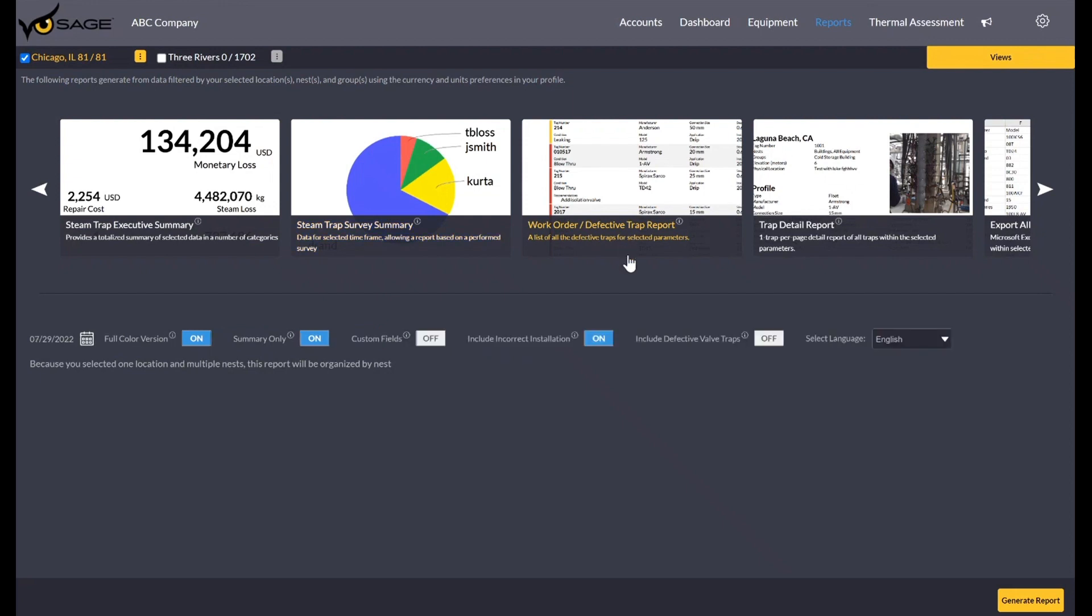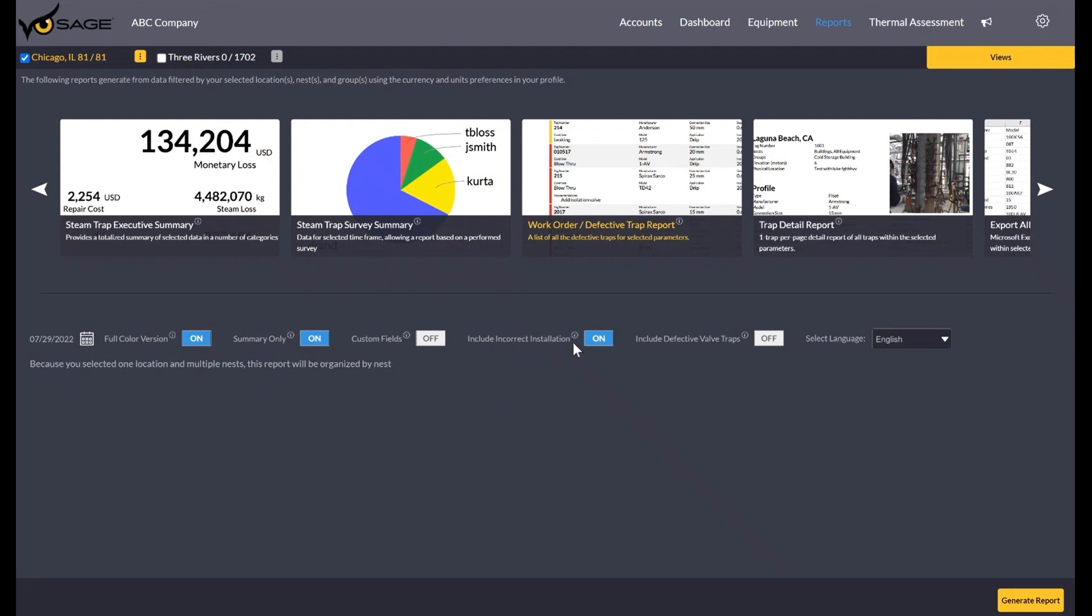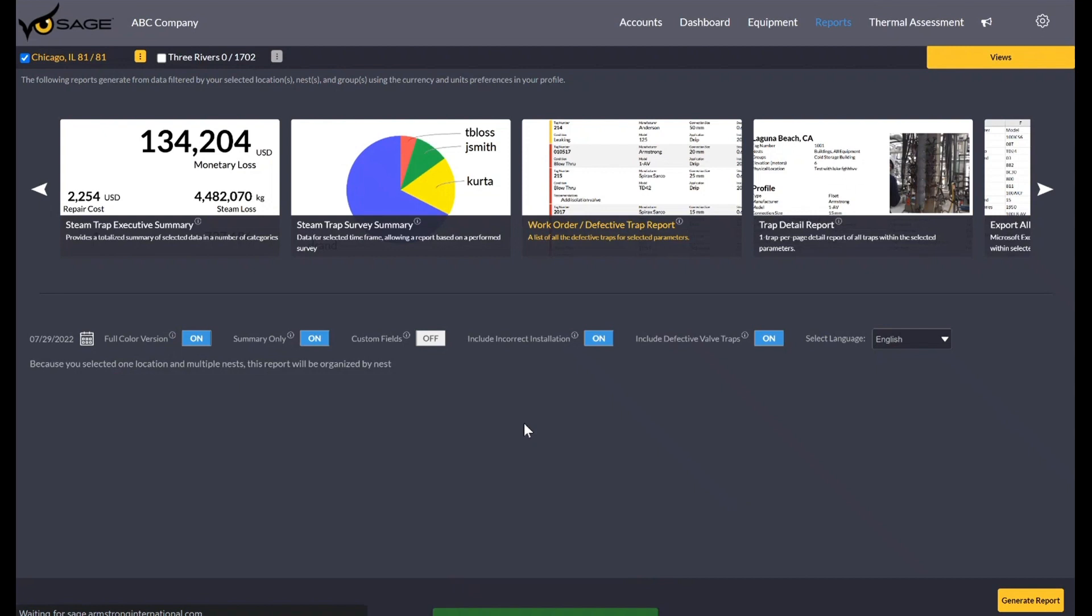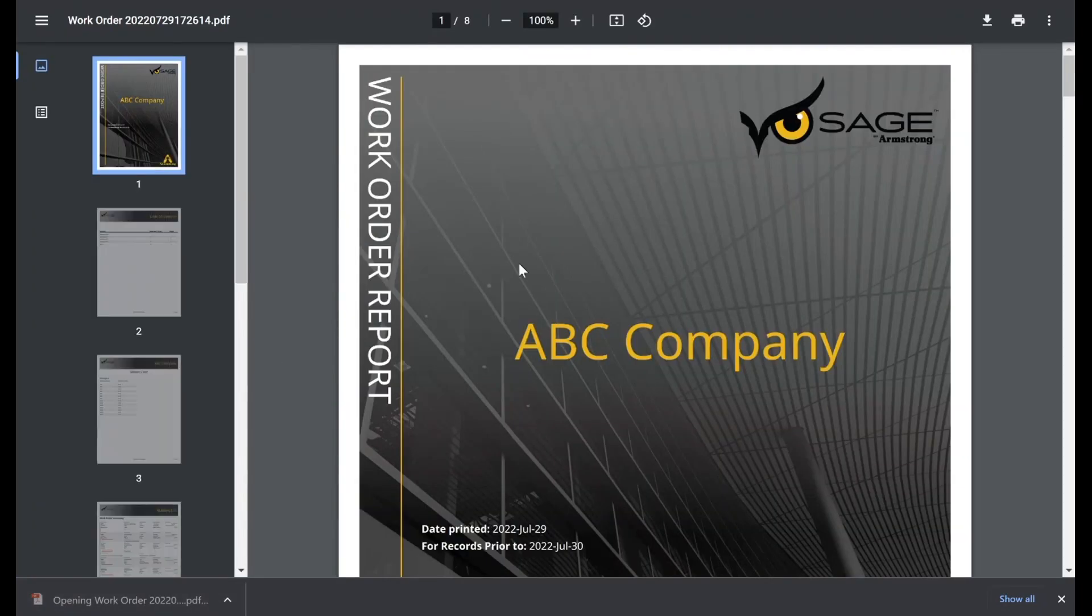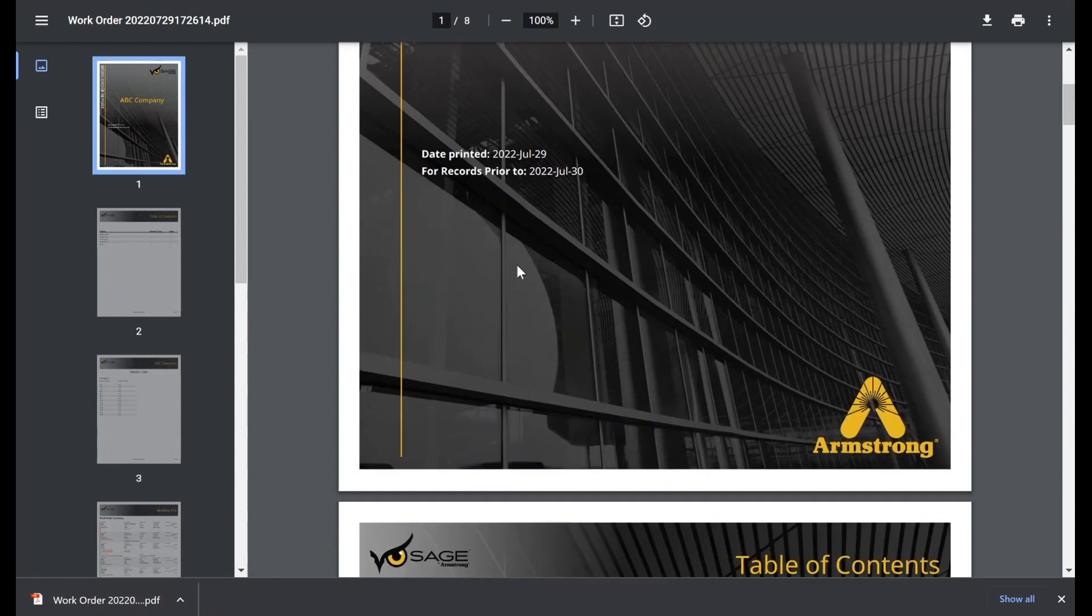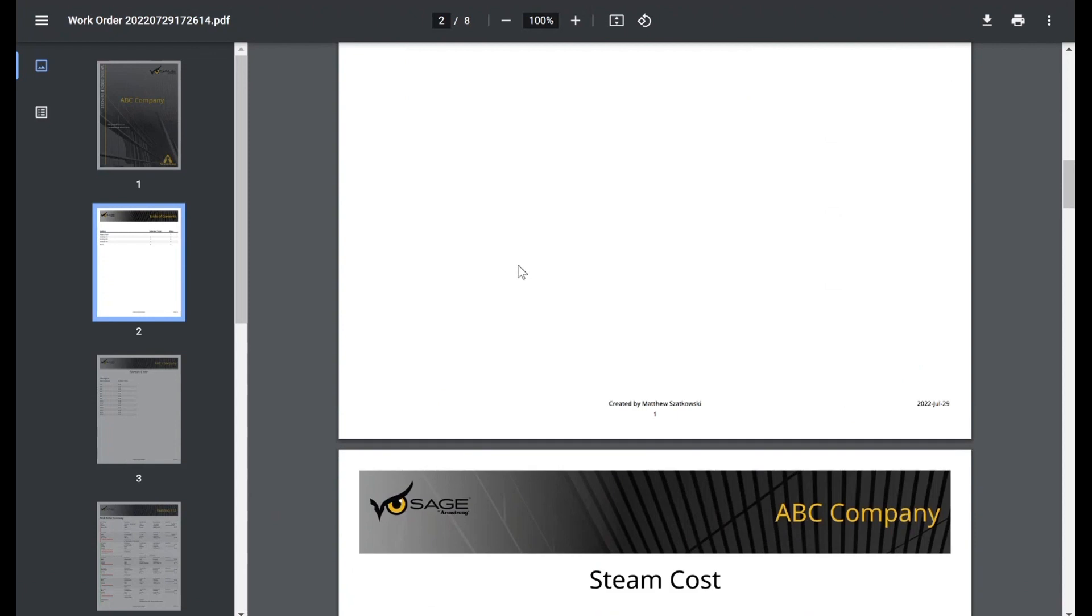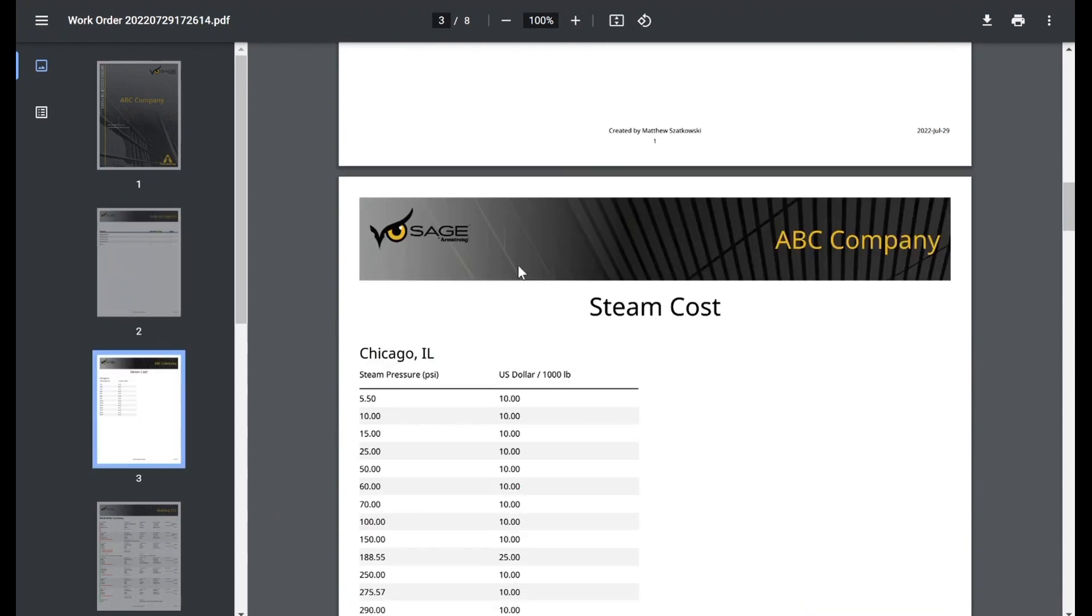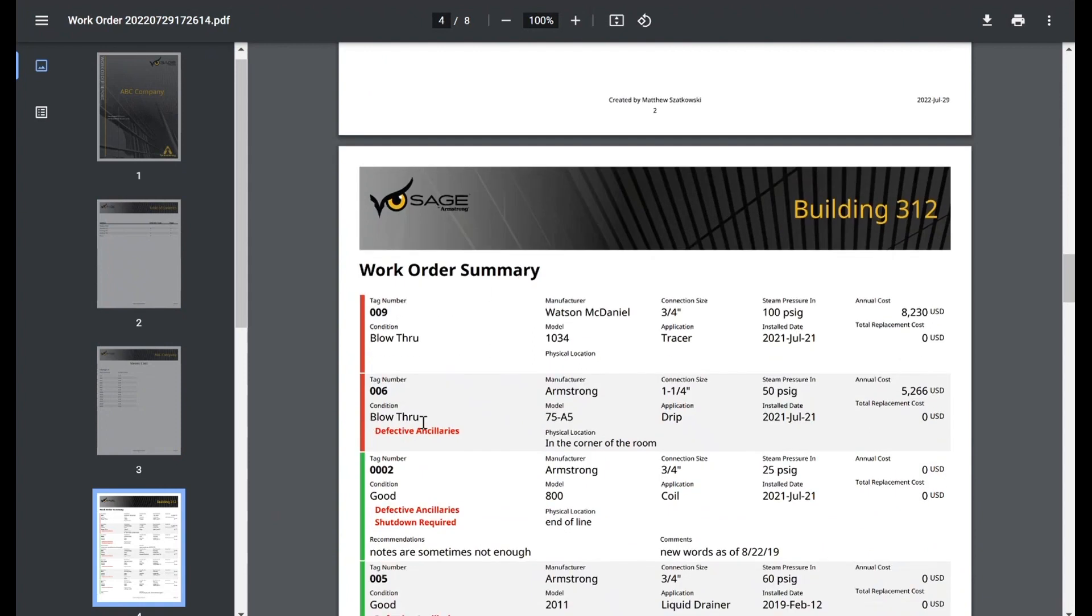The next report here is the work order defective trap report. This is going to report on any failures in our system. Again, the default, like the steam trap executive summary, is today or the day you've entered the system. You can always run a historical version if you'd like to look at historical records. And this one by far has the most customization to the report. As you can see, you have the option to include the incorrect installation toggle and defective valves. So as I went over both of those, if you had toggled this because maybe some piping was incorrectly installed or the trap itself, or the valve around it was defective and you want to include that in the report. If I generate this version of it, we're going to see all of our traps that had a failed state, but then also good traps that had the incorrect installation toggle set or had valves that were in a failed state, like a leaking valve or a plugged valve.